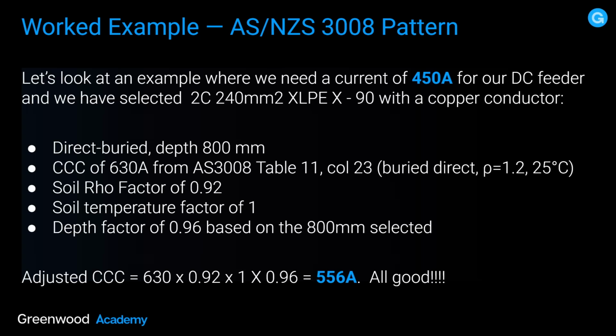So effectively, what these figures mean is that you've got your original 630 amps based on 25 degrees with a thermal resistivity of 1.2 at a certain buried depth. And from there, if you increase any of those factors, you're going to get a reduced current carrying capacity, and we're going to look at that. So the adjusted current carrying capacity is 630 amps, the original figure, times 0.92, which is a soil factor, times 1, which is a soil temperature factor of 1 in this case at 25 degrees C, times 0.96, which is the derating factor based on an 800mm burial depth, and we've got the final result is 556 amps. So that's all good. We're well over the 450 amps that we need for this particular cable run.